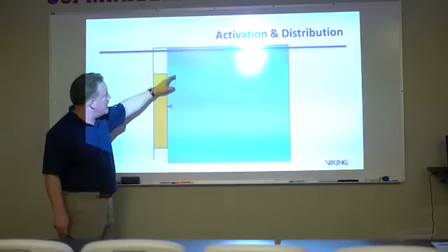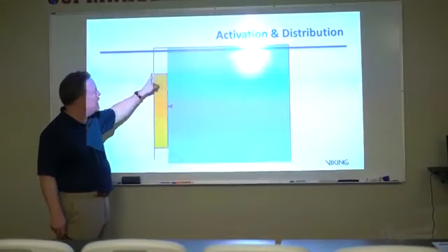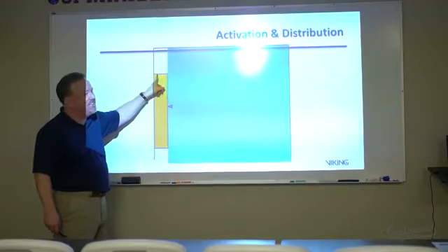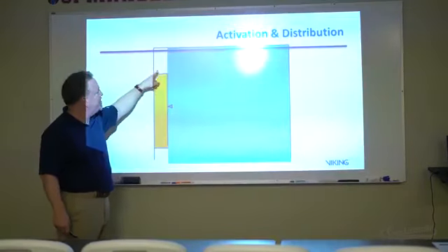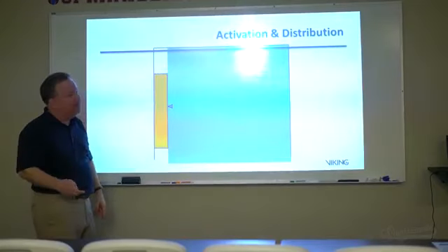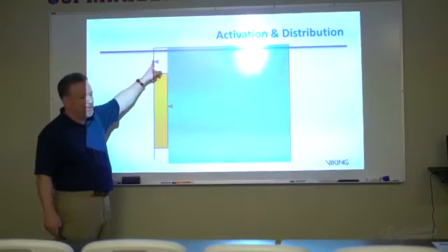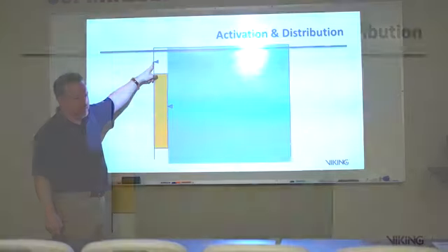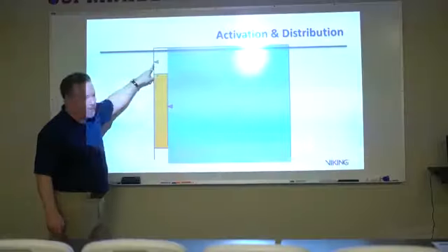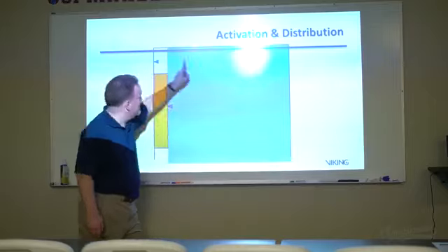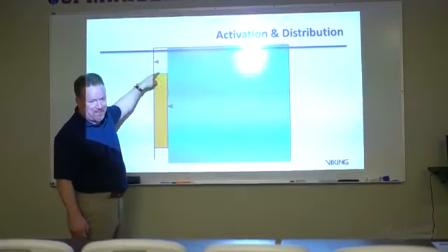Sure enough, I looked around the corner. This is only about 15 inches deep, maybe 15 inches by 2 feet. And sure enough, there was a sprinkler there. Now, how much of the floor area is this sprinkler actually protecting? Hold on. That right there. Everything it reaches. Well, yeah, but this has already got everything else. This thing really is only going to protect this.